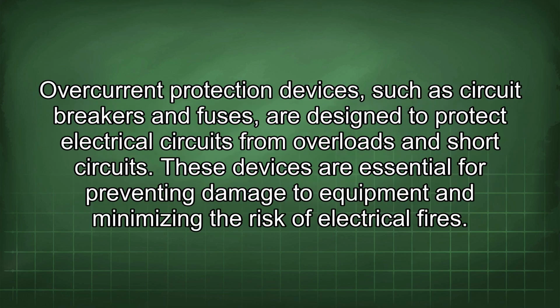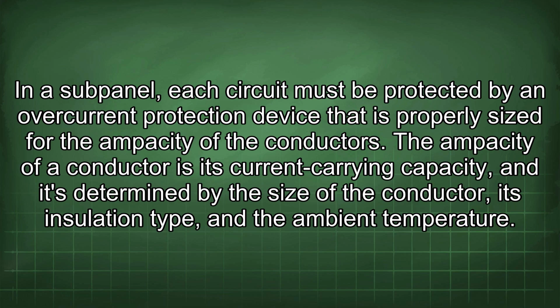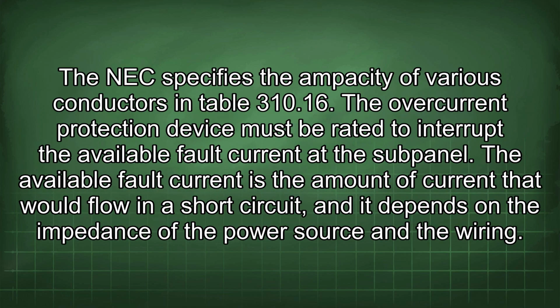Overcurrent protection devices, such as circuit breakers and fuses, are designed to protect electrical circuits from overloads and short circuits. These devices are essential for preventing damage to equipment and minimizing the risk of electrical fires. In a subpanel, each circuit must be protected by an overcurrent protection device that is properly sized for the ampacity of the conductors. The ampacity of a conductor is its current carrying capacity, and it's determined by the size of the conductor, its insulation type, and the ambient temperature. The NEC specifies the ampacity of various conductors in Table 310.16.